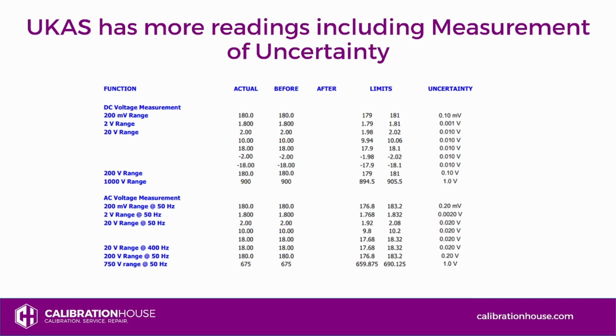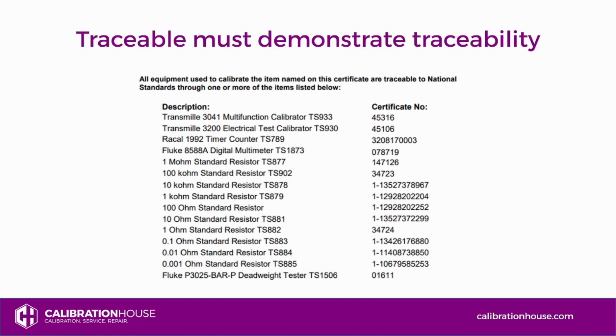A UKAS certificate generally has more readings that include measurement of uncertainty. So you can see the uncertainty of this electrical calibration on the right-hand side here. Traceable certificates tend to have fewer readings, and they don't include measurement of uncertainty. A traceable certificate must demonstrate how it is traceable.